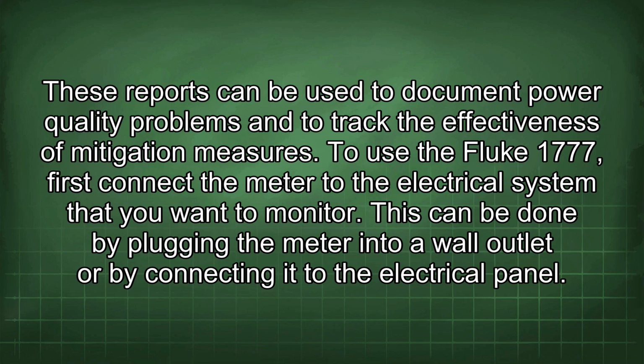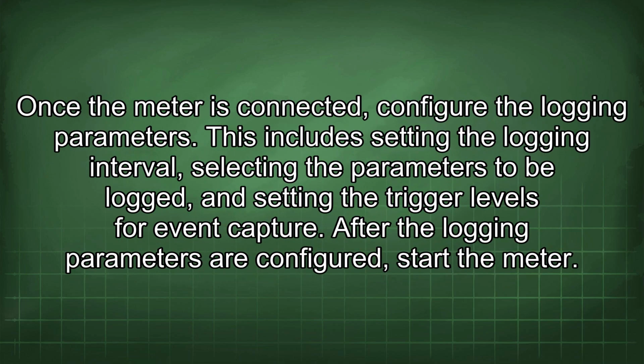To use the Fluke 1777, first connect the meter to the electrical system that you want to monitor. This can be done by plugging the meter into a wall outlet or by connecting it to the electrical panel. Once the meter is connected, configure the logging parameters. This includes setting the logging interval, selecting the parameters to be logged, and setting the trigger levels for event capture.